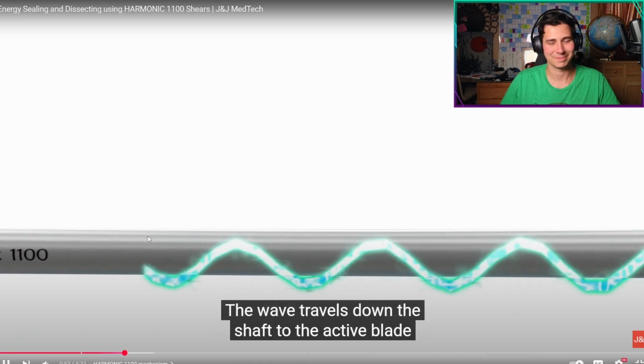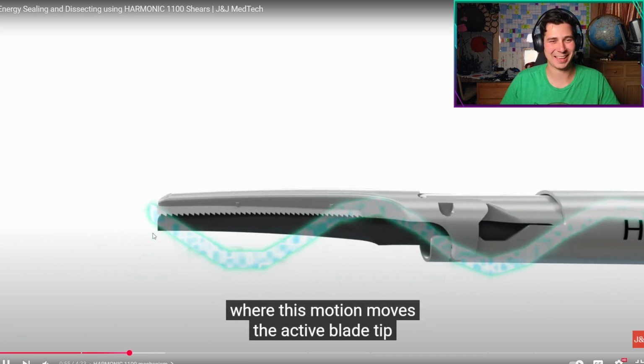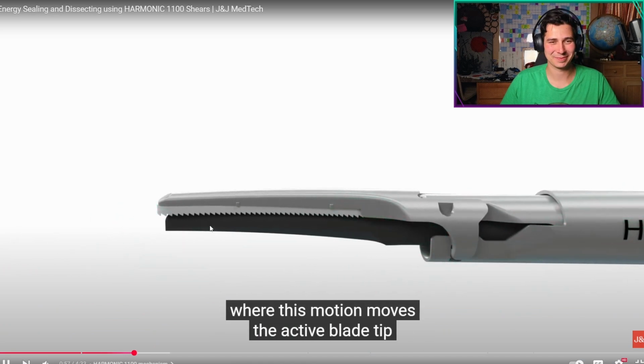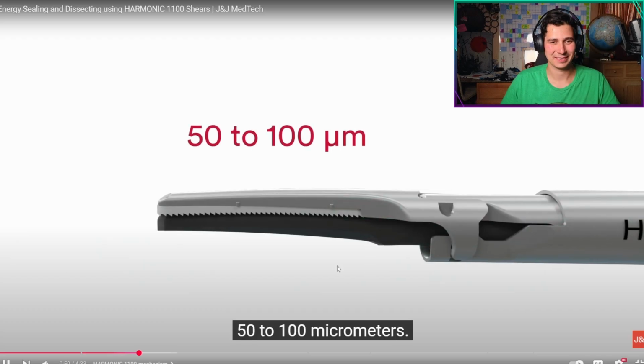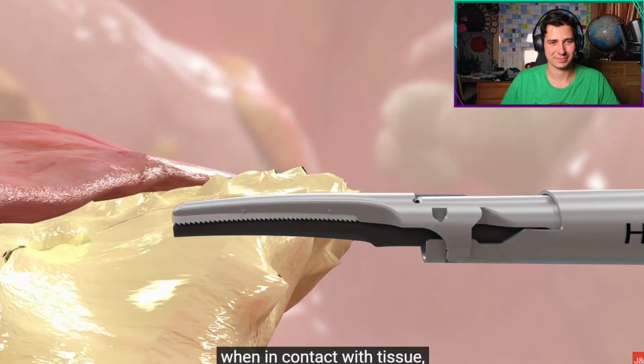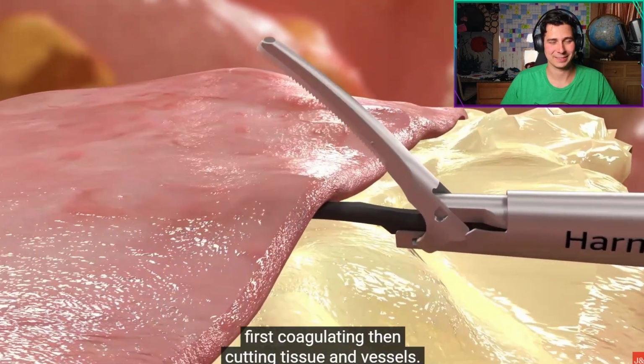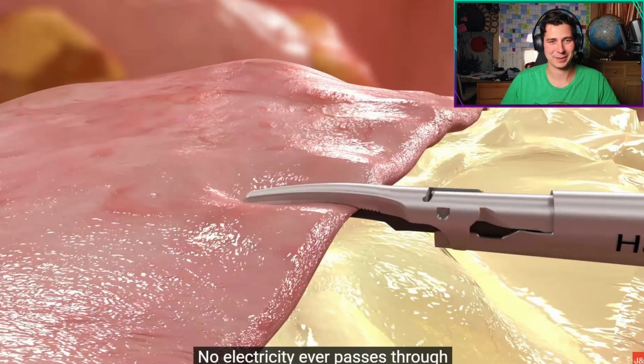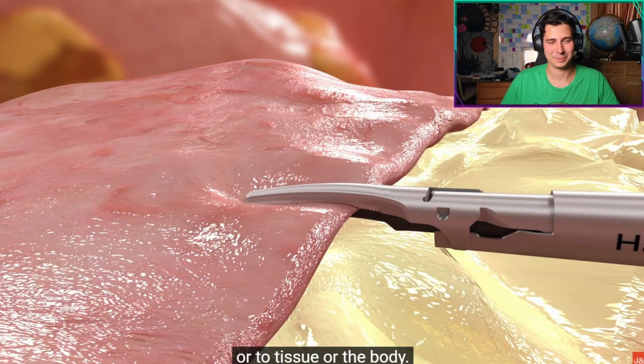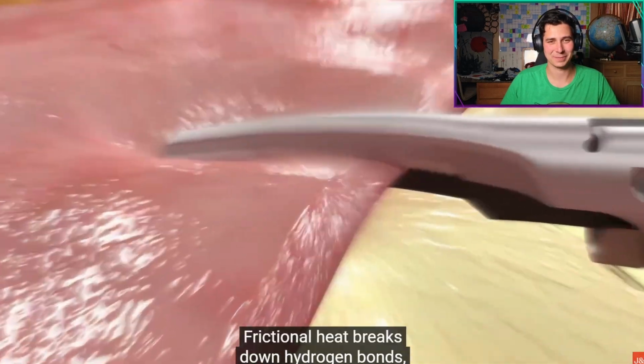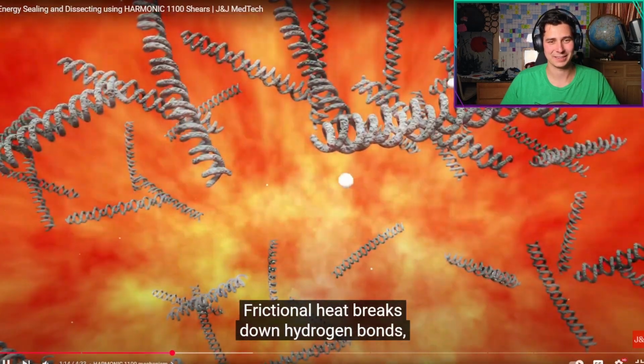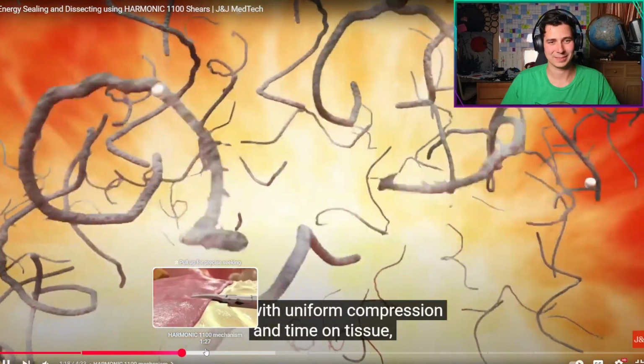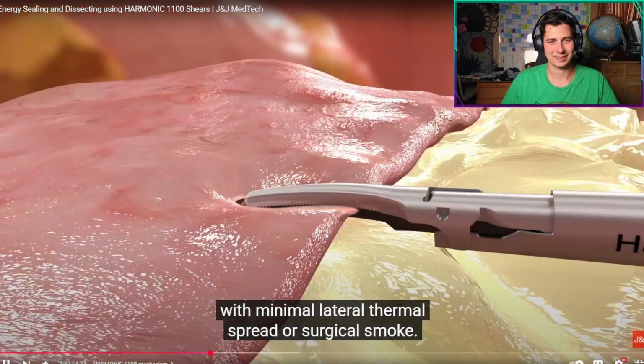The wave travels down the shaft to the active blade, and this motion moves the active blade tip 50 to 100 micrometers. This motion creates frictional heat when in contact with tissue, first coagulating, then cutting tissue and vessels. No electricity ever passes through to the body. Frictional heat breaks down hydrogen bonds, denaturing proteins and creating a sticky coagulum, along with uniform smoke. Cut and seal.